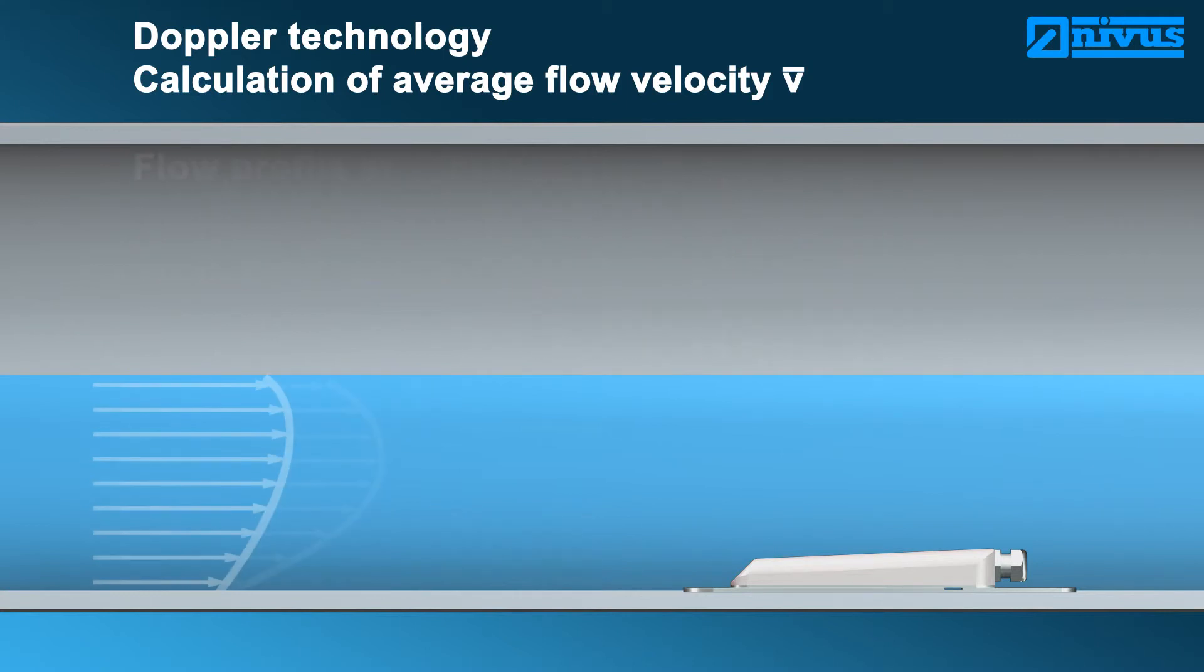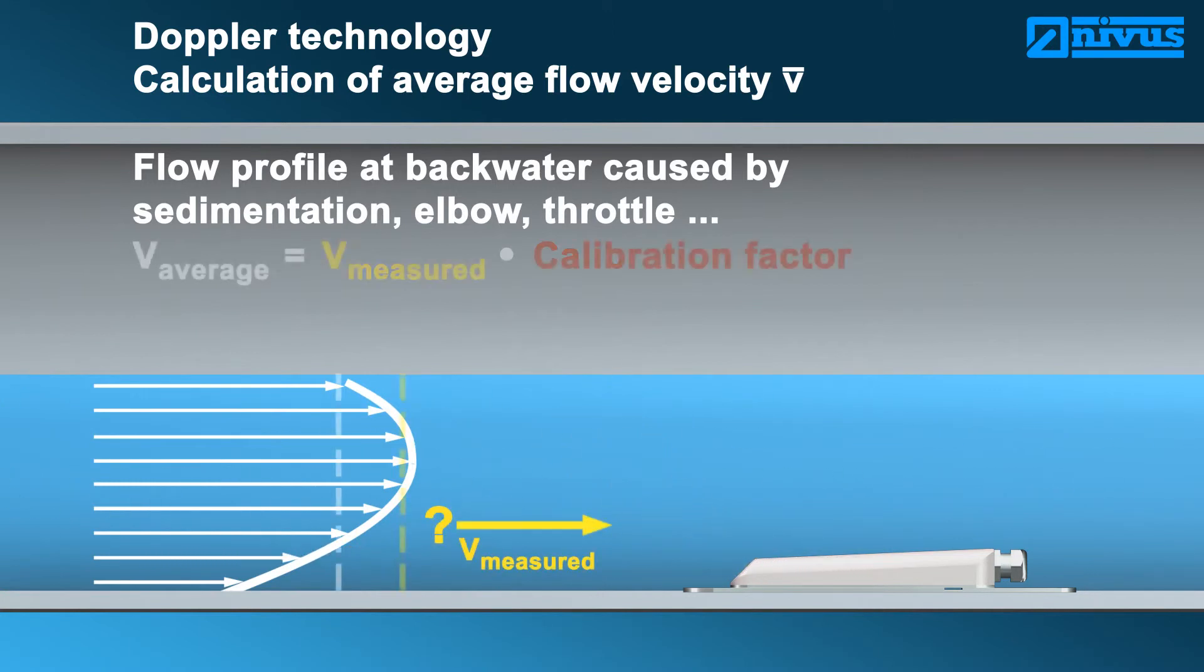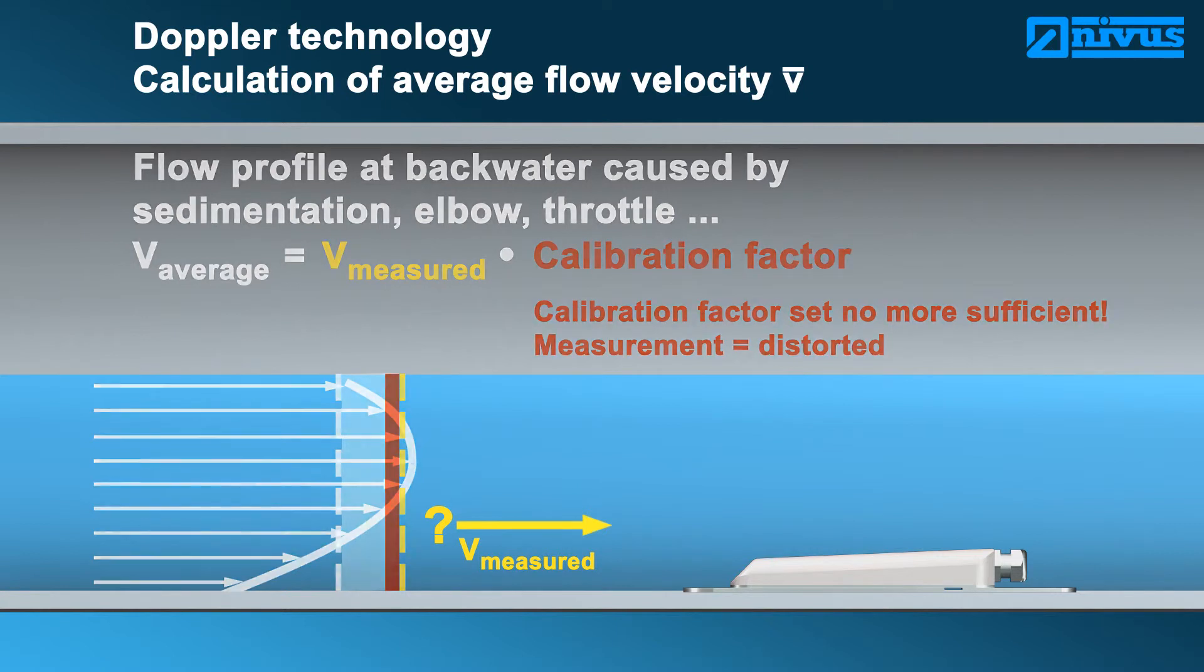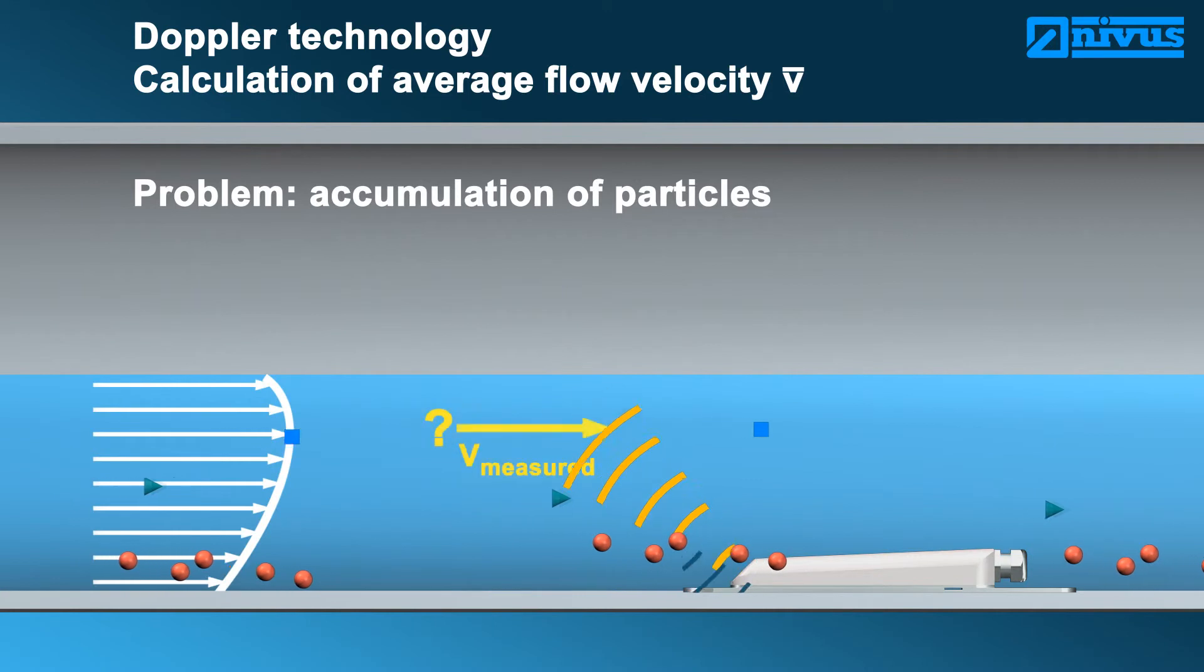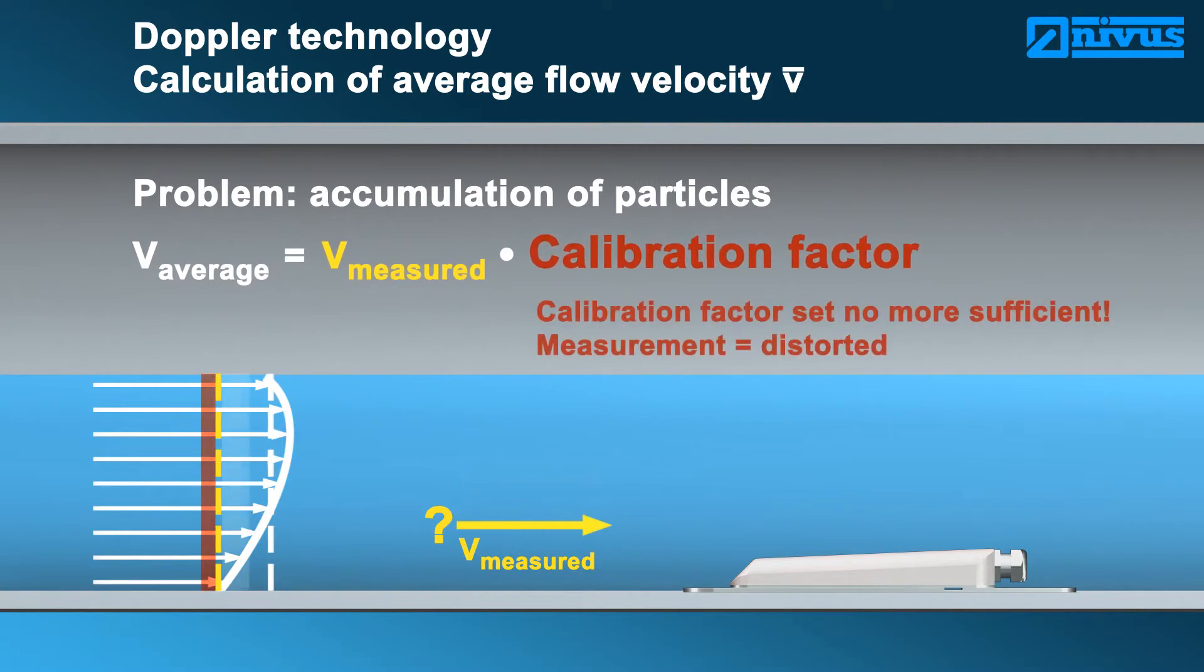The flow conditions will change even in case of backwater formation caused by sedimentation, elbows, or throttle equipment. The original calibration factor is no longer valid and the measurement results are faulty. Accumulation of particles generates a stronger measurement signal and is determined by the sensor as the measurement spot. A local variation therefore creates a distorted reading which varies from the calibration.